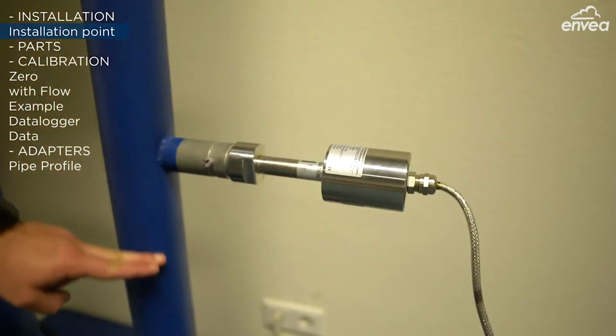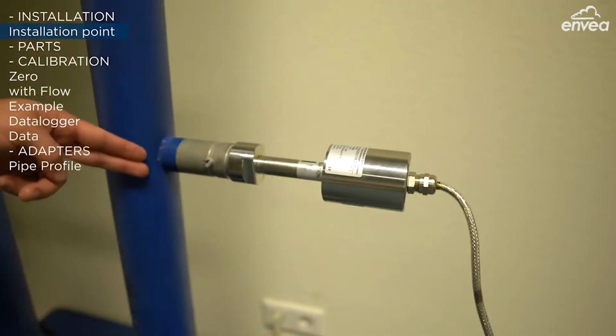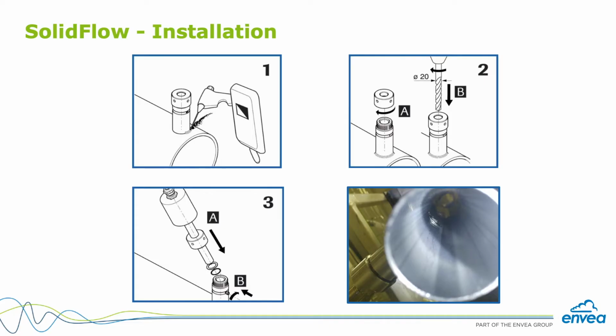The installation is a pretty good subject to talk about. It's basically welding these well-known sockets along the pipe, flushing with the inside. We drill a hole through this socket, and then we come with the sensor. The sensor is then screwed into the socket, and the tip of the sensor should be flush inside. We don't want any part to be moving or wearing over time.